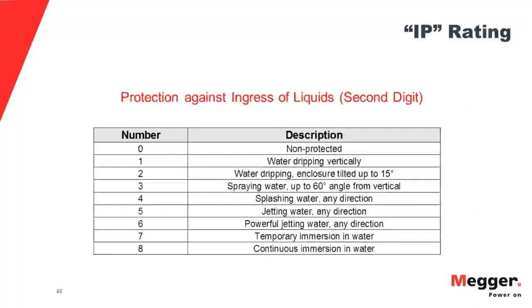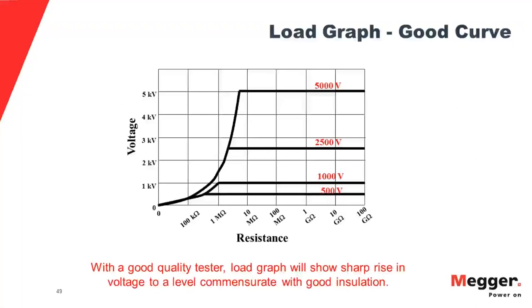Okay, load graph. Again, you want to see a very quick, very sharp rise up to the voltage at which you intend to test, and you don't want your voltage to load down at the low end of the insulation spectrum until you get to what is actually not good insulation. So you note this is a good load graph. This shows you, for instance, that at 5,000 volts, by the time you're up to about 5 megohms, which would be the minimum acceptable insulation resistance for a 5,000 volt circuit, you're getting 5,000 volts out of your tester.